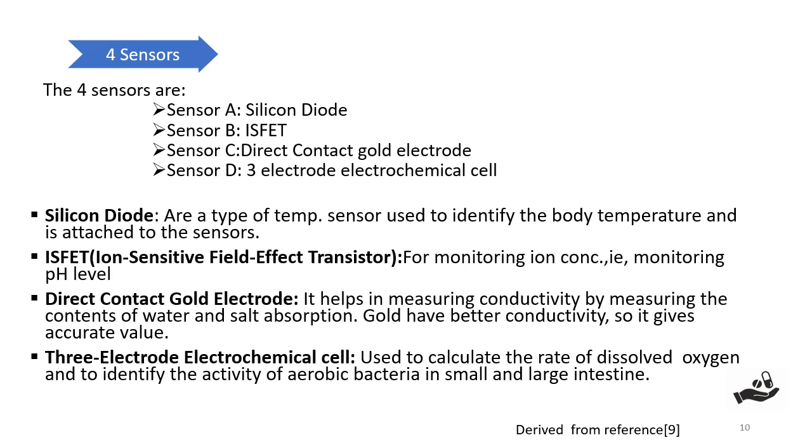Then we will be looking at the ion sensitive field effect transistor, that is the second sensor. This type of electrode contains a transistor coated with a chemically sensitive material to measure pH in solution and moist surfaces. As the potential at the chemical active surface changes with the pH, the current induced through the transistor varies. A temperature diode simultaneously monitors the temperature at the sensing surface. The pH meter gives a temperature compensated pH reading that correlates the change in current and temperature.